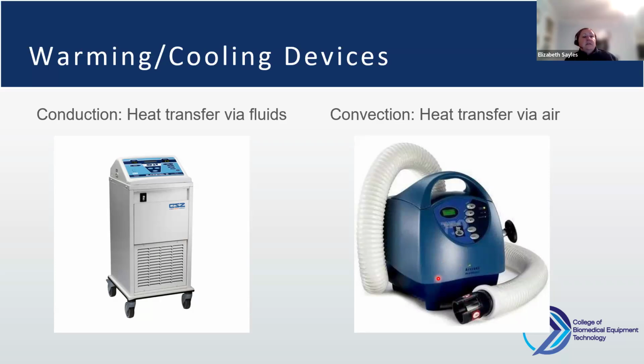This is the most prevalent device you're going to see from a convection perspective - you'll see these Bair Huggers, and a lot of them have agreements where you're not really paying for any of the parts, and a lot are getting sent out for replacement. Aside from replacing a couple filters and potentially the keypad, you're going to be doing function checks on them, testing the over and under temp alarms to make sure those are working properly. But yeah, not a lot of maintenance with these.